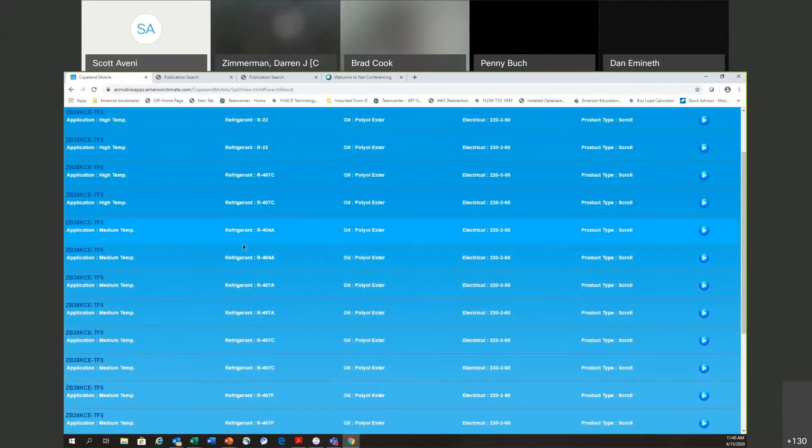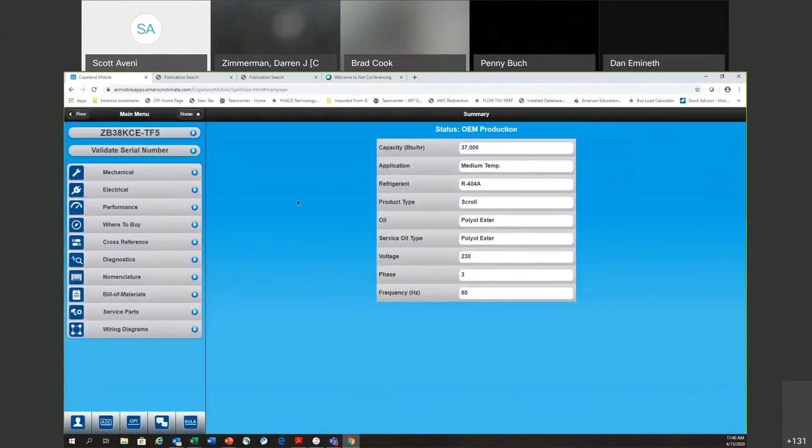I'm going to go with 404A. For each refrigerant there is a 50 Hz and 60 Hz option — you'll want to pick 60 Hz here in the US. The first page that comes up is the summary screen. You get a generic capacity number of 37,000 BTUs, it's a medium temp application, it has POE oil, and the voltage is 230 volts, three-phase, indicated by our TF5 voltage code.